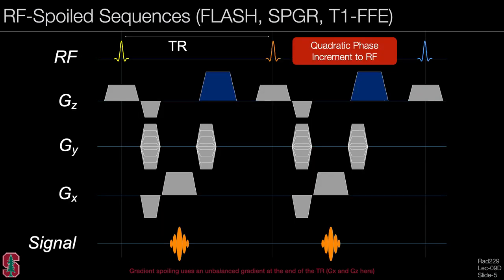The RF spoiled sequences, which go by the names FLASH, SPGR, or T1FFE, look a lot like the gradient spoiled sequence, except for one change: the RF pulse phase is incremented with a quadratic phase increment, which we will explore.